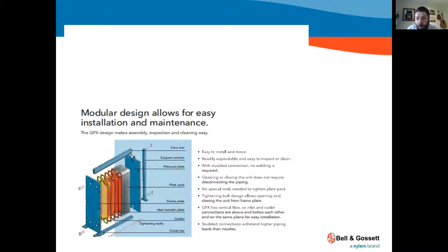You have your guide bar on the bottom, carry bar on top. They connect to the frame plate and have a support bar in the back. The frame plate at the front, that's a fixed plate. That thing's footed, bolted in, that's solid. The heat transfer plates are in the middle. They're doing all the real work. All of these plates are considered the plate pack altogether. So that's your medium in the middle. That's where the water is actually going through between those plates and their gaskets.